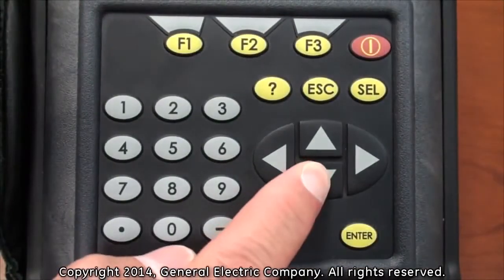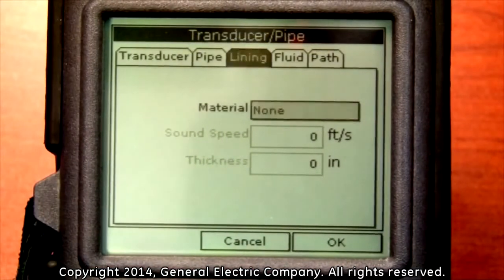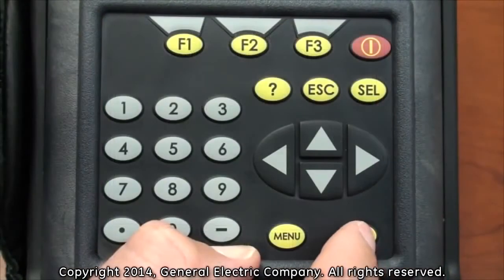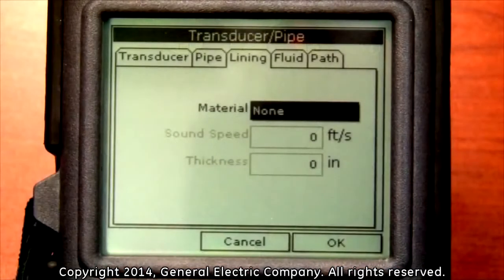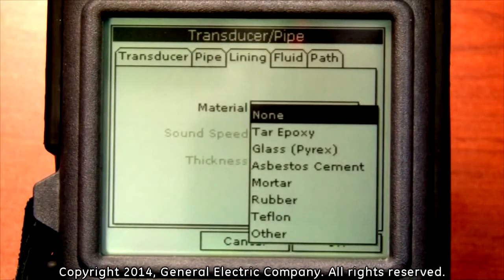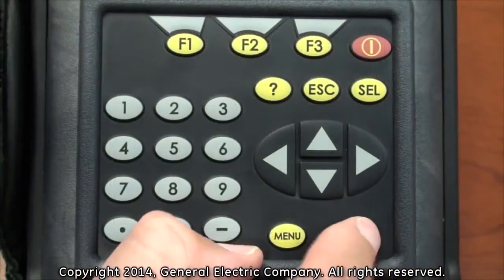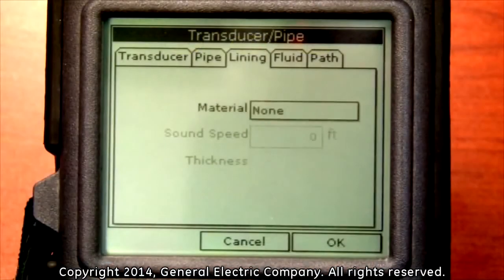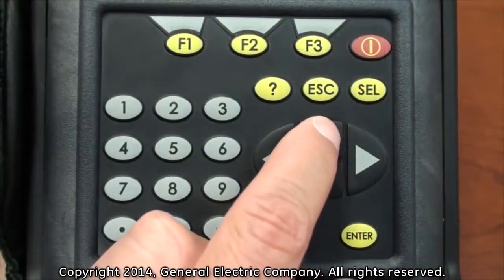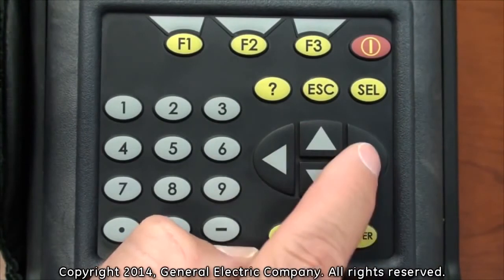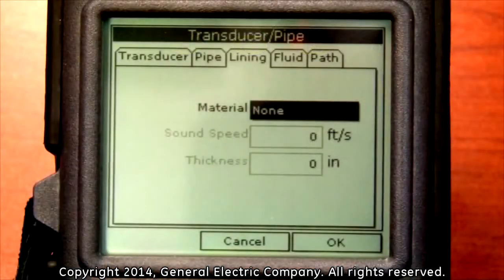Press the down arrow key to select the material field. Press the Enter button to view available options. If there is no lining material, choose None and press the Enter button. Press the up arrow key to go back up to highlight lining and then press the right arrow key to select the fluid menu.